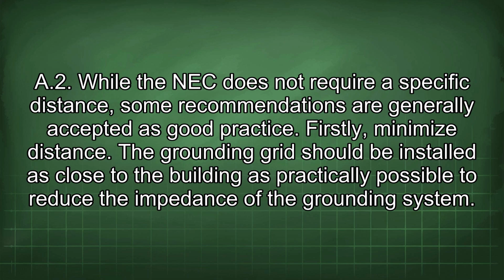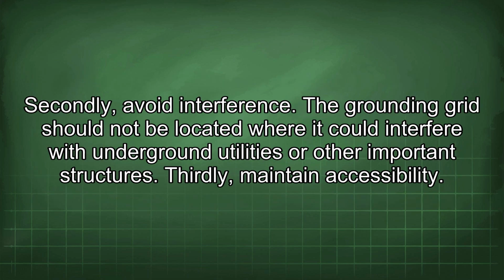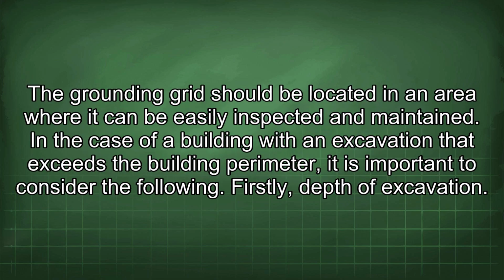Firstly, minimize distance. The grounding grid should be installed as close to the building as practically possible to reduce the impedance of the grounding system. Secondly, avoid interference. The grounding grid should not be located where it could interfere with underground utilities or other important structures. Thirdly, maintain accessibility. The grounding grid should be located in an area where it can be easily inspected and maintained. In the case of a building with an excavation that exceeds the building perimeter, it is important to consider the following. Firstly, depth of excavation.